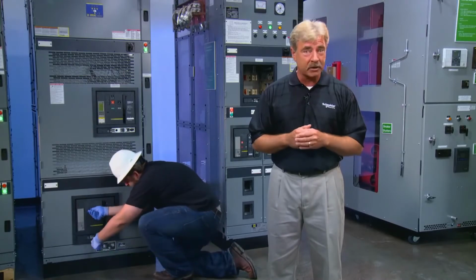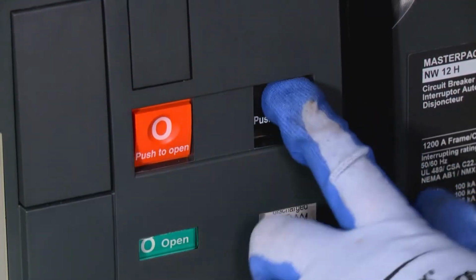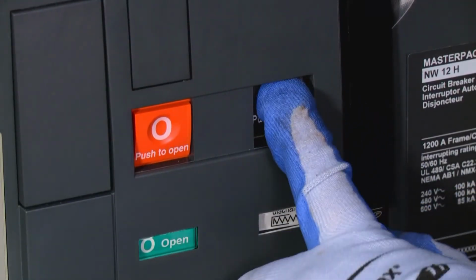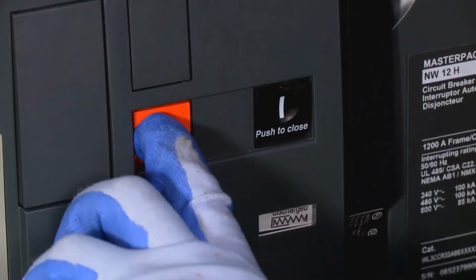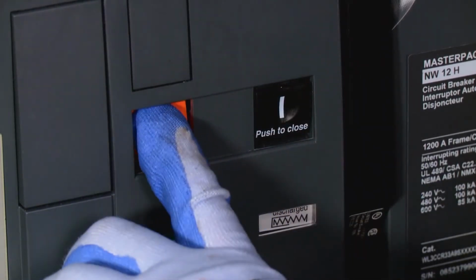First, make sure the breaker is turned off. Press the Press to Close button to discharge the spring, and then press the Press to Open button to open the contacts. For draw-out circuit breakers, rack the breaker into the disconnected position.